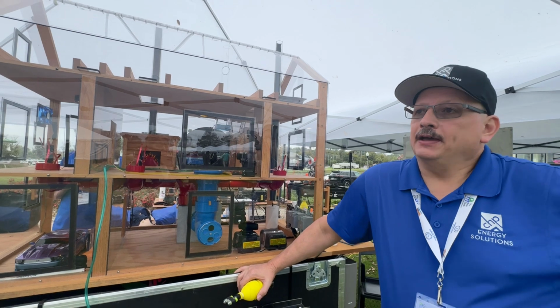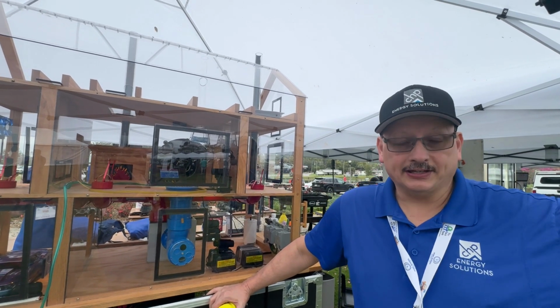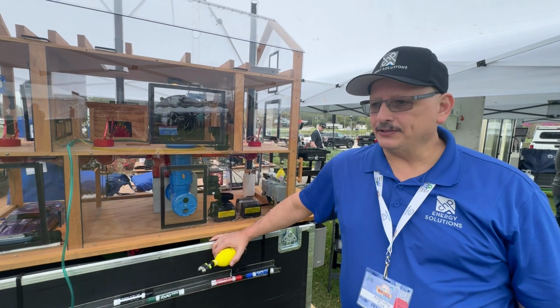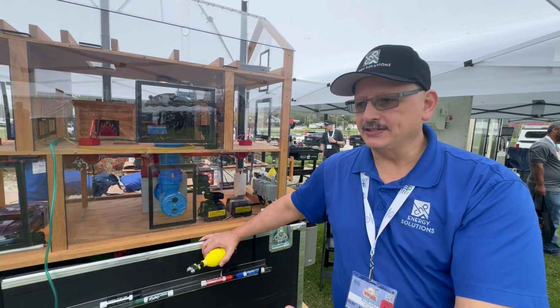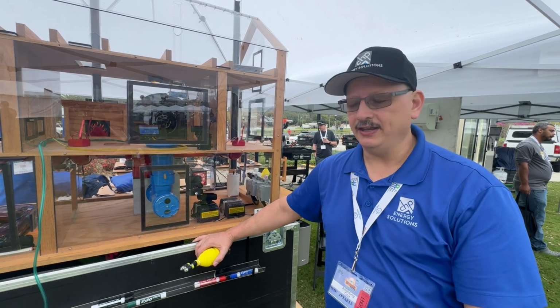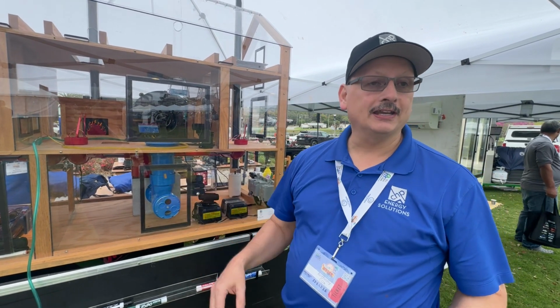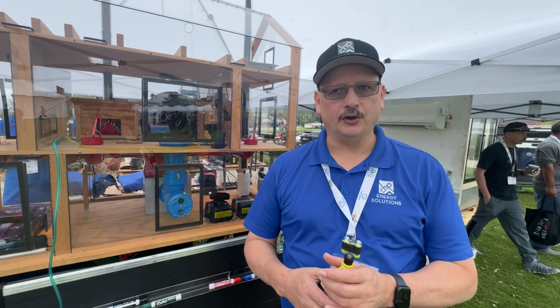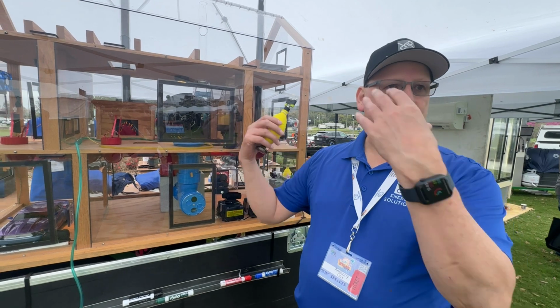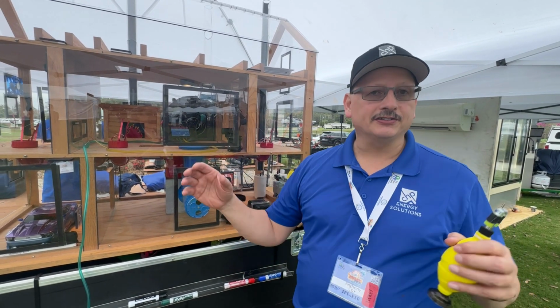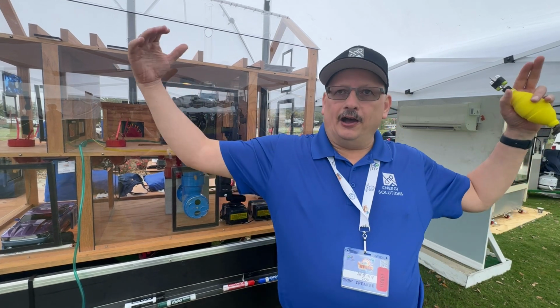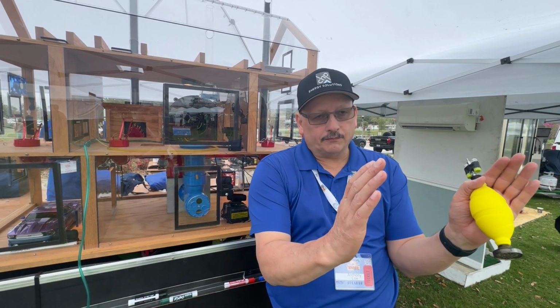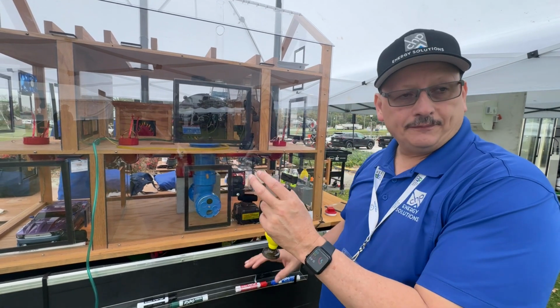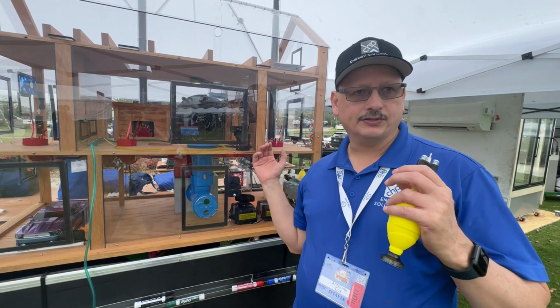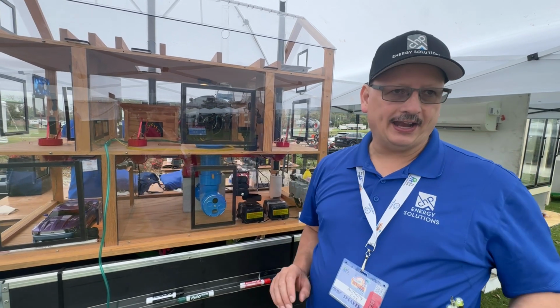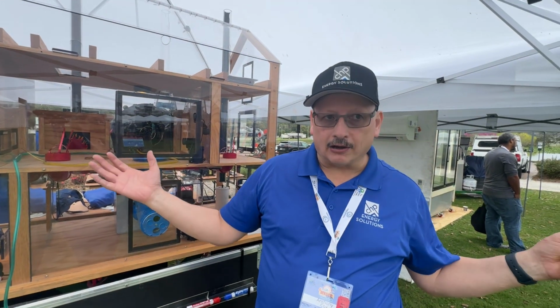Some of them don't know it affects things as much as it does. Sometimes they just get the complaint, like the house isn't heating or cooling well, or it's too humid, or maybe pulling in smells from the house, which I'll show with a return leak in a minute. Unless they've educated themselves on what we call building science, understanding that the house is a whole system, they might just be working on the furnace or air conditioner without realizing everything else is connected. Especially with forced air systems, moving air, stuff travels with that air, whether it's heat, humidity, or indoor air quality issues.